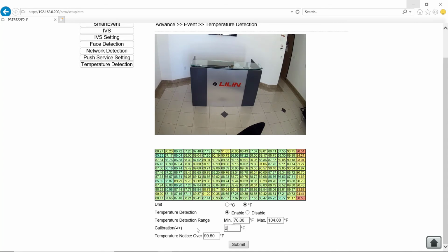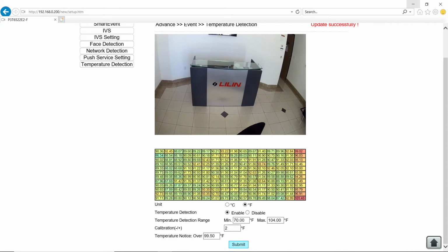Toward the bottom here, we can actually see a field for calibration. So we can go ahead and enter a plus or minus number and then submit. And then we can see each of the thermopile sectors adjust up or down based on what we've entered in the calibration field. As a best practice, we recommend that you use an infrared thermometer or some other similar FDA-approved device to scan the subject's head and then use that to inform what you enter into the calibration field.